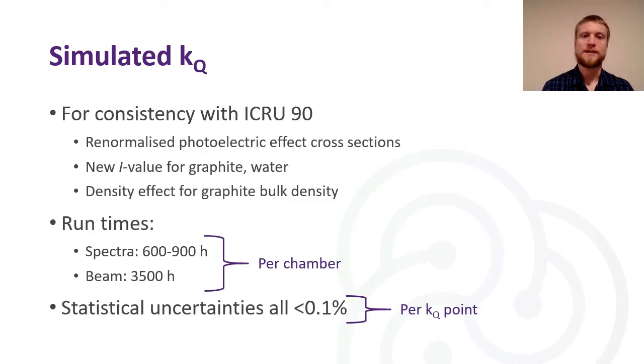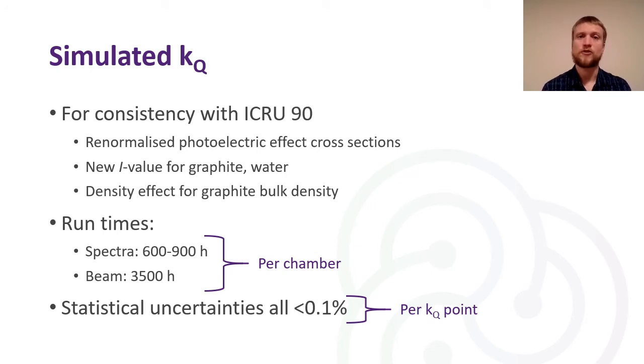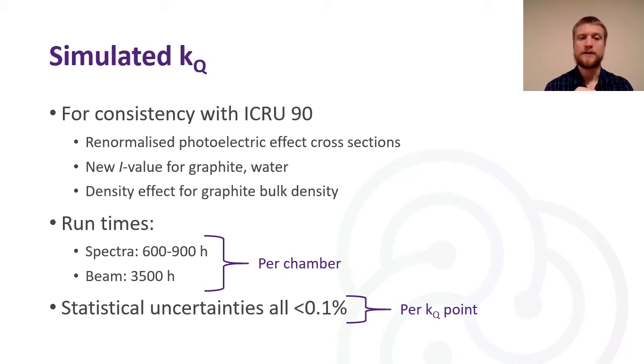For consistency with ICRU report 90, we modelled the re-normalised photoelectric effect cross-sections, used the new mean excitation energy values for graphite and water, and used the density effect for graphite at bulk density rather than the density it appears in the chambers. The runtimes for the tabulated spectra were on the order of 600 to 900 hours per chamber combined across all energies, and for the BEAMnrc LINAC models they were closer to 3,500 hours per chamber. Statistical uncertainties for each submitted point were less than 0.1% per KQ point.